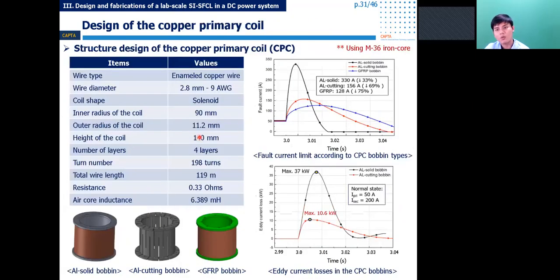In case of the copper primary coil design, a 2.8 millimeter diameter enameled copper wire was selected. It can withstand a current up to 64 ampere. So there is no problem with the normal current of 50 ampere of the DC system. In the bobbin design, the material and the structure were considered to minimize the eddy current loss. Based on the cost and material properties, 3 kinds of bobbin were considered, including the aluminum solid bobbin, the aluminum cutting bobbin, and the GFRP bobbin.